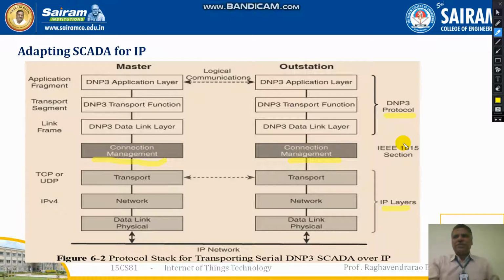Now, master stations may process multiple DNP3 data link layer frames from a single UDP datagram, while DNP3 data link layer frames cannot span multiple UDP datagrams. Single or multiple connections to the master may get established while a TCP keep-alive timer monitors the status of the connection. Like this, the connection between DNP3 and IP communication works.